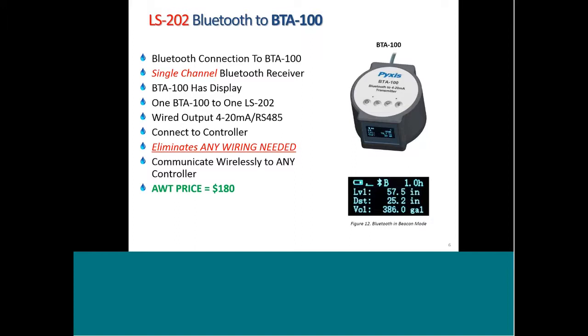It basically takes the Bluetooth signal from your tank level monitor, the LS202, remotely, and then it will redisplay the value that's on the tank itself. But in the back of that device are 4 to 20 and Modbus wiring, open wires, and that can be wired directly to any conventional controller that receives those inputs. So it allows you to transfer the data wirelessly from your tank to your controller as an analog input. The list price on this device is $250, and we offer a discount to ETI and AWT members of $180. And it, again, is powered by the controller that you're connecting to.